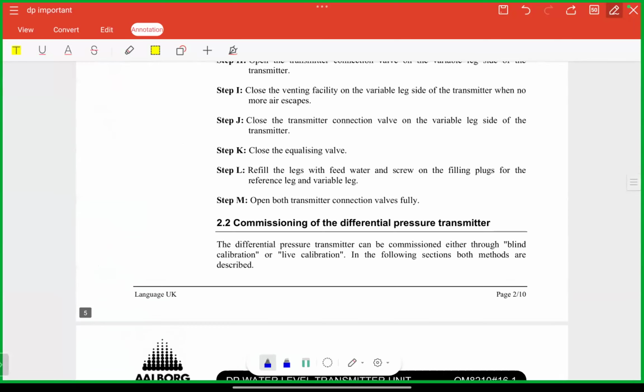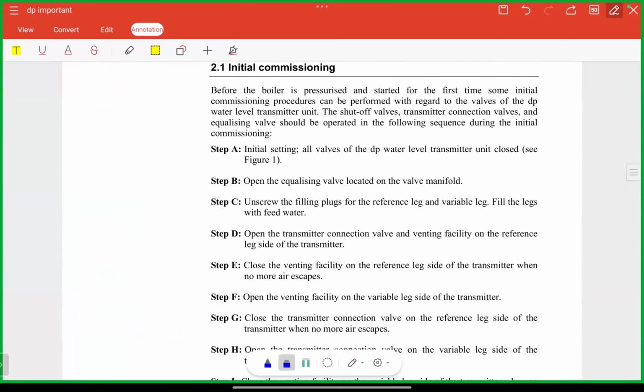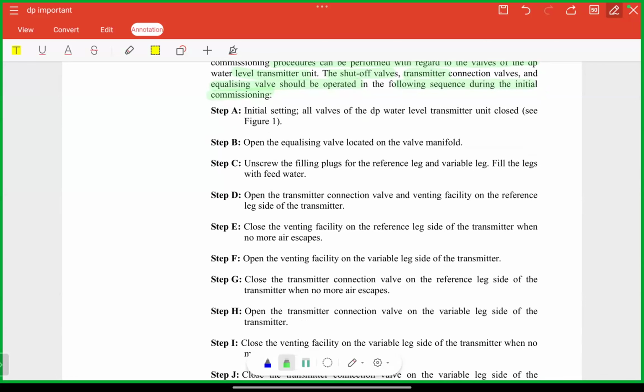So, initial commissioning of your DP transmitter. Let's go step by step here. Before the boiler is pressurized and started for the first time, some initial commissioning procedures can be performed with regard to the valves of the DP water level transmitter: shut-off valves, transmitter connection valves, and equalizing valve should be operated in the following sequence. Step A, initial setting: all valves of the DP water level transmitter unit should be closed. Step B, open the equalizing valve located on the valve manifold. Step C, unscrew the filling plugs for the reference leg and variable leg and fill the legs with water.